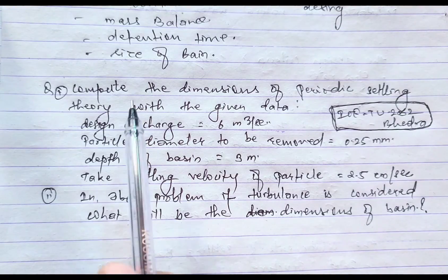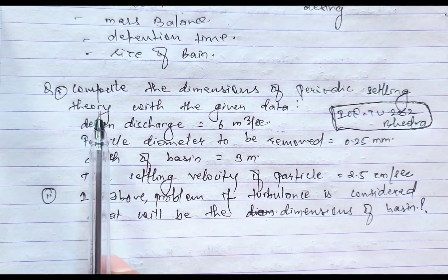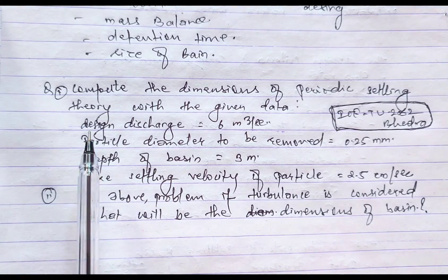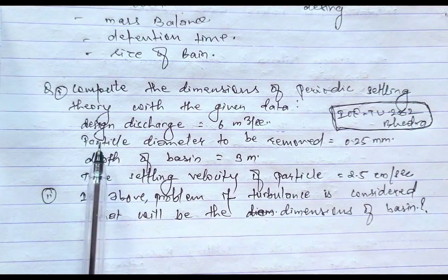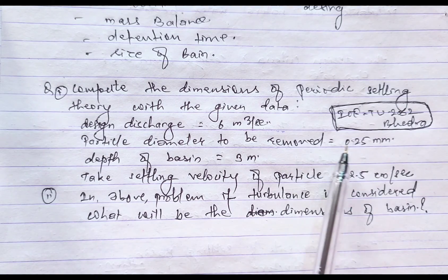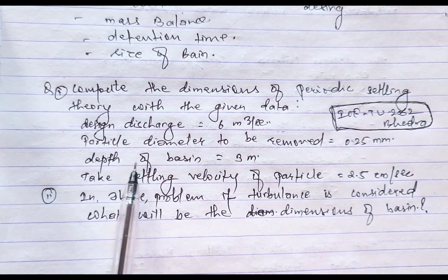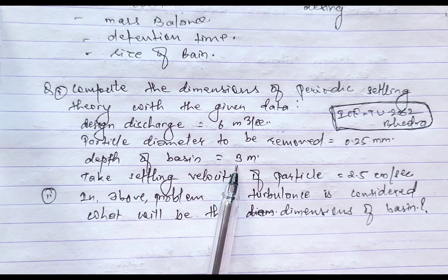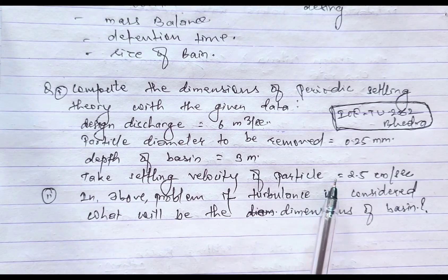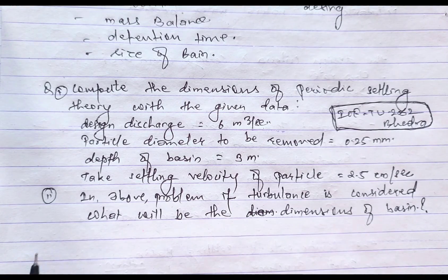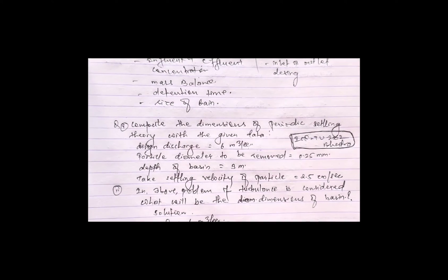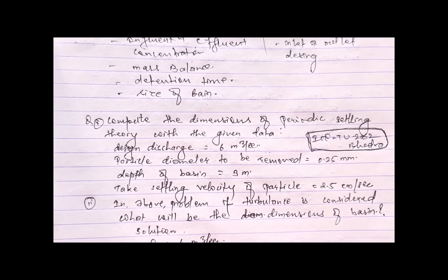The given question is: compute the dimensions of the settling basin using particle settling theory with the given data — design discharge Q = 6 m³/s, particle diameter to be removed d = 0.25 mm, depth of basin D = 3 m, settling velocity of particles w = 2.5 cm/s. Also, if turbulence is considered, what will be the dimensions of the basin? Let's start solving.